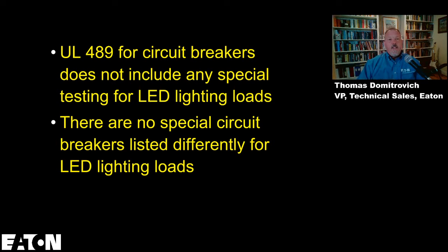UL 489 for circuit breakers does not include any special testing for LED lights or LED loads. There are no circuit breakers listed differently for LEDs.